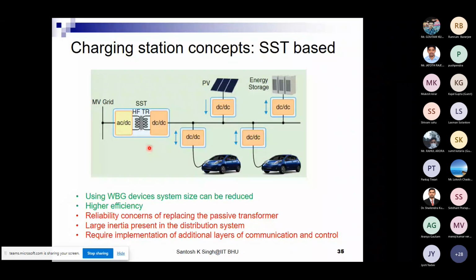So instead of having a very big low frequency transformer, its size can be as small as a briefcase—you can bring it in and connect it, and that's it. But at this moment, one serious problem with these SSTs is that their efficiency is not as good as our low frequency transformer. So though we say it's higher efficiency, that's only when we consider other factors into account.